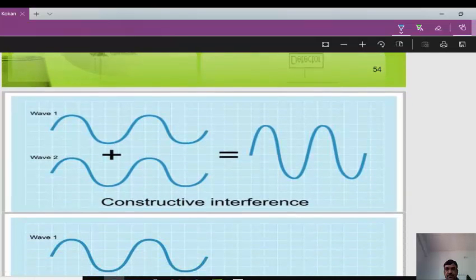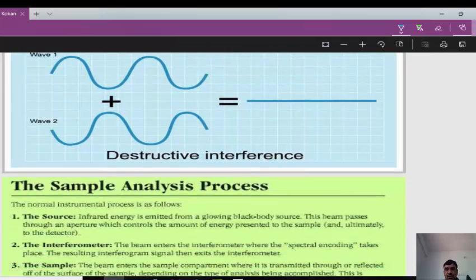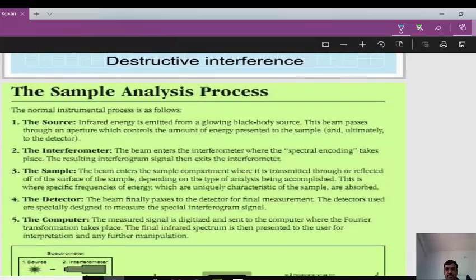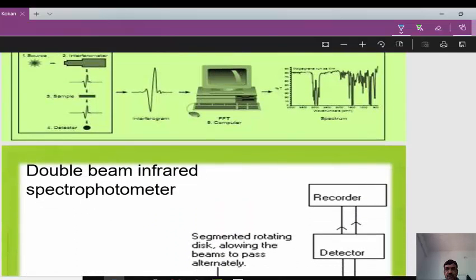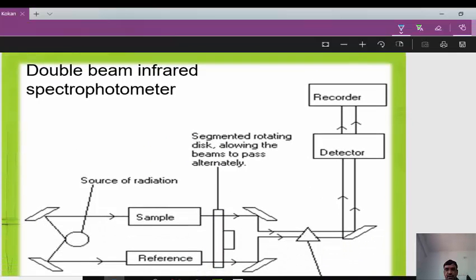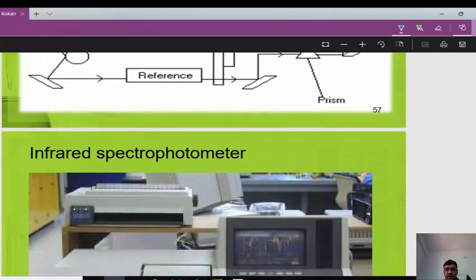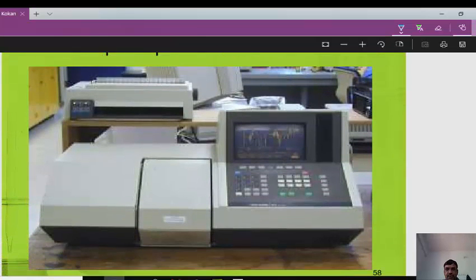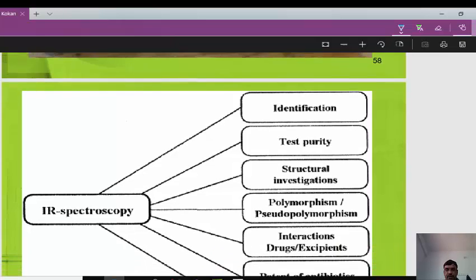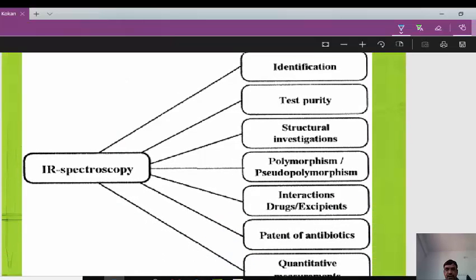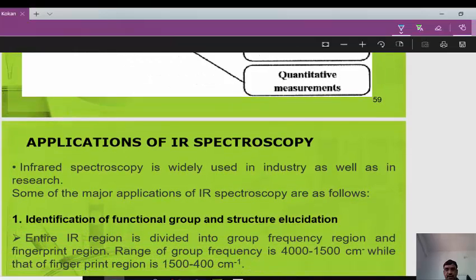The conventional IR spectrometer uses dispersive or non-dispersive frequency-domain spectra. FT-IR (Fourier Transform IR) offers high signal-to-noise ratio using time-domain spectra. In FT-IR, constructive and destructive interference of two waves creates an interferogram; the process flows from source → interferometer → sample → detector → computer. A double-beam infrared spectrometer uses two beams: one through the sample and one as reference.